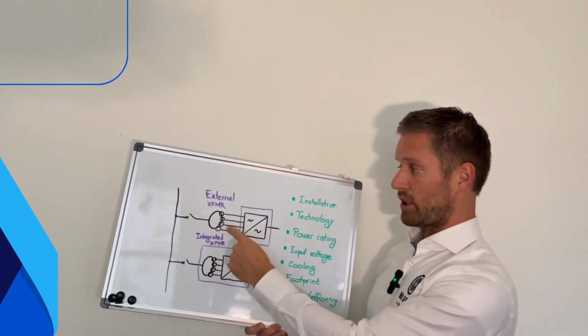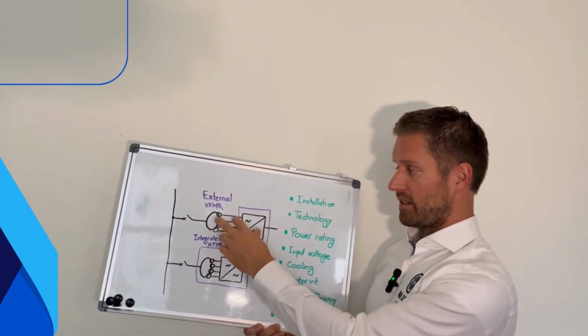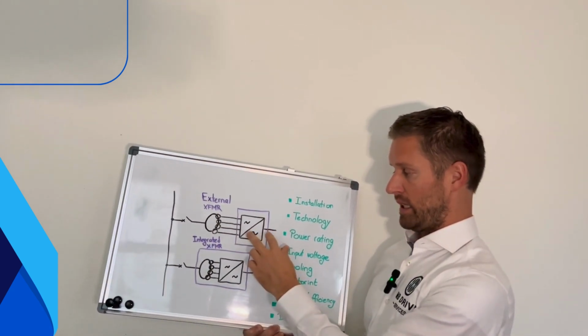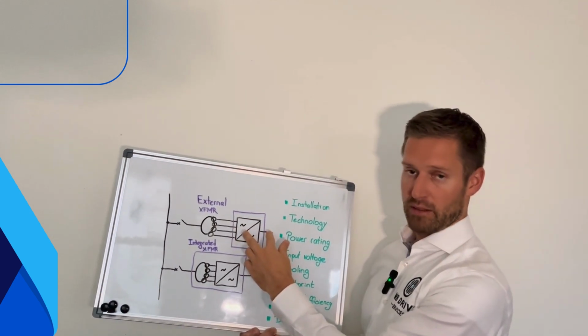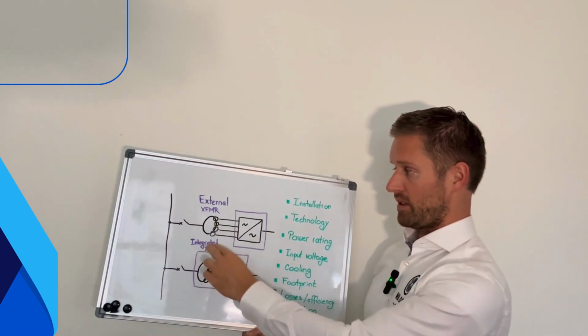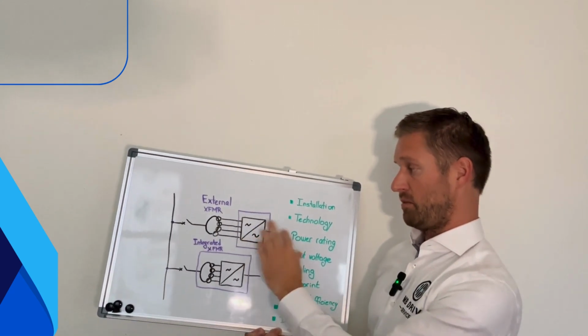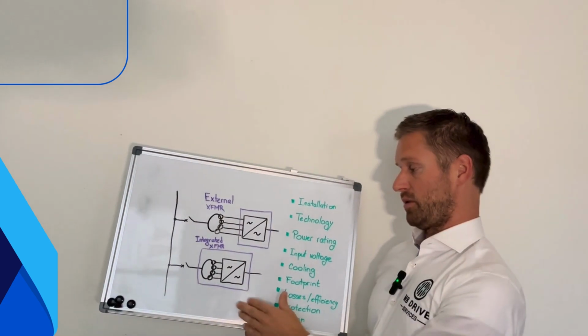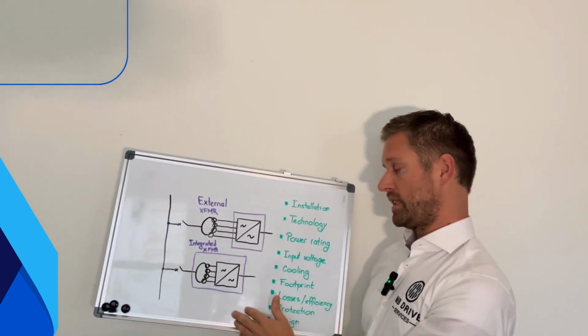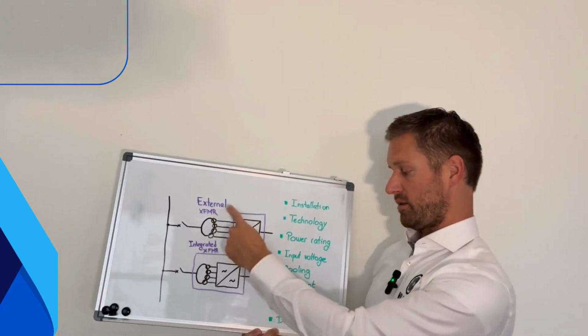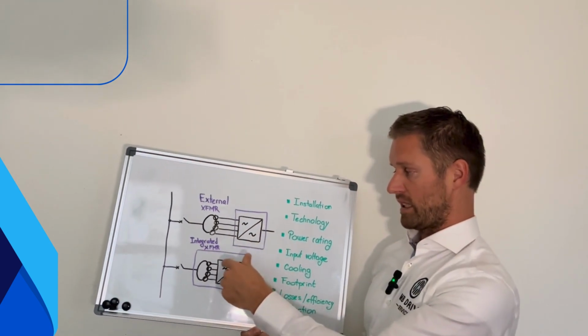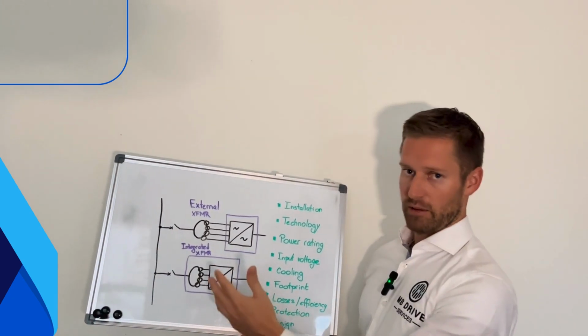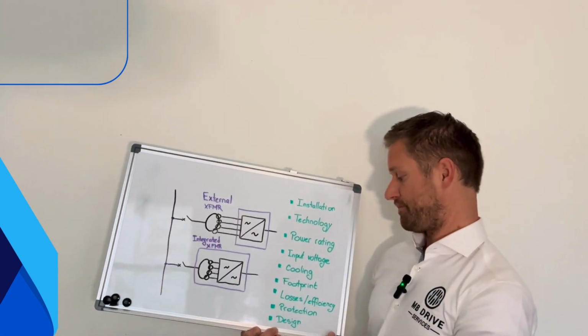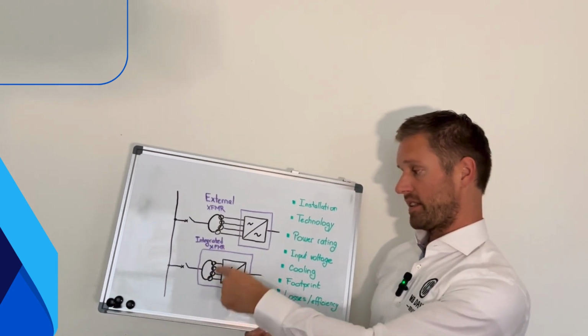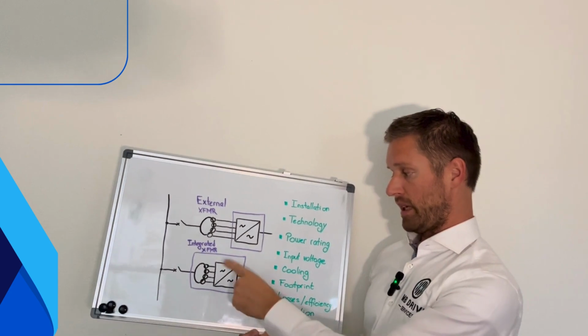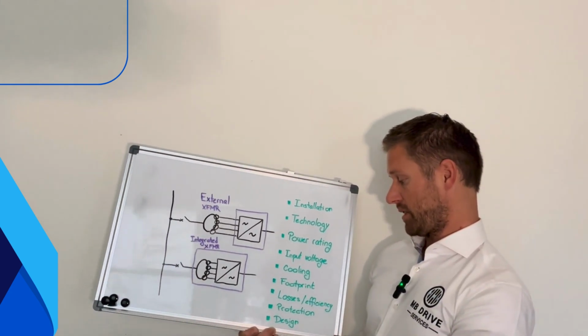If the transformer is external, then the transformer needs its own protection. It's not by default protected by the VFD. So someone needs to take care of the transformer protection. It can be the VFD manufacturer, maybe if he supplies the whole drive system, or another company, or the end user himself, but someone needs to take care and install the corresponding equipment for the protection and the implementation, the settings for the relay, and so on. With the integrated transformer, the settings for the relay are already delivered by the VFD manufacturer.